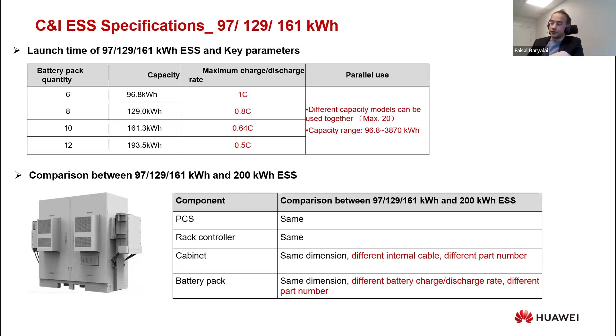But if it's not possible to increase the modules, of course when the existing battery modules reach end of lifespan, you can replace them with the same amount. However, the CMU unit, the whole control system, is programmed for that specific number of modules - if it's 6 modules, it's programmed for 6. If one module is defective and needs changing, you can do that, but you cannot just go from 6 to 8 modules, adding 2 extra. It's an interesting point though, since our customers want this option, which is why this is an ongoing discussion with Huawei about how it will work in the future.